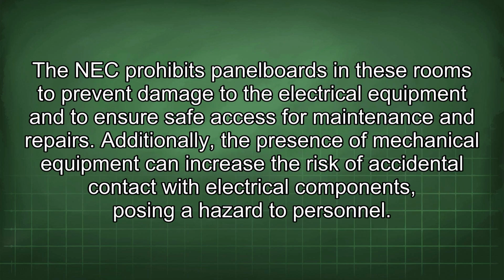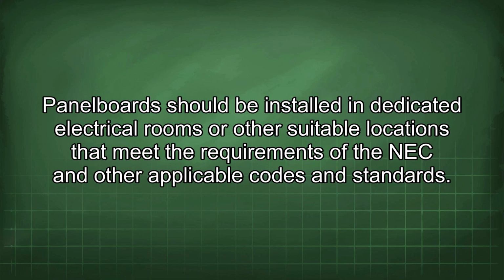The NEC prohibits panelboards in these rooms to prevent damage to the electrical equipment and to ensure safe access for maintenance and repairs. Additionally, the presence of mechanical equipment can increase the risk of accidental contact with electrical components, posing a hazard to personnel. Panelboards should be installed in dedicated electrical rooms or other suitable locations that meet the requirements of the NEC and other applicable codes and standards.